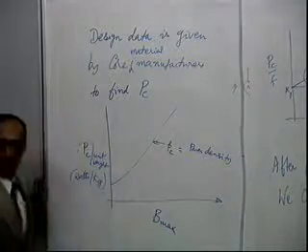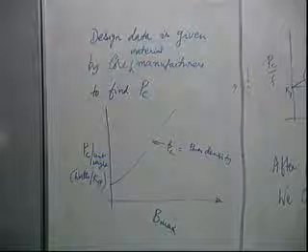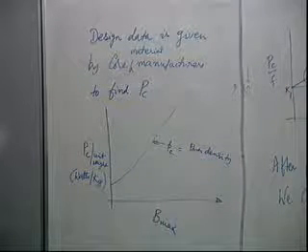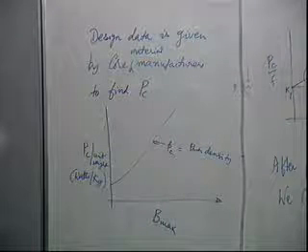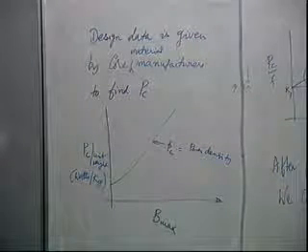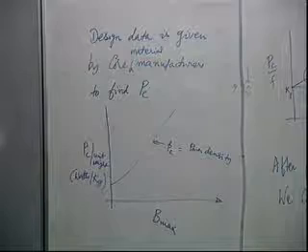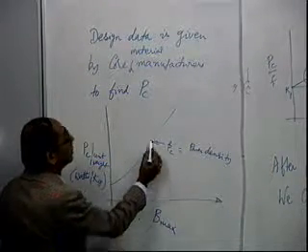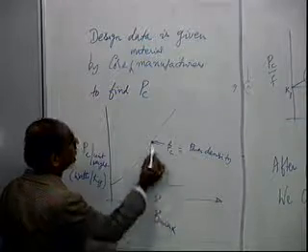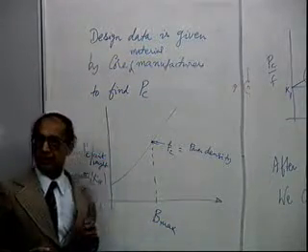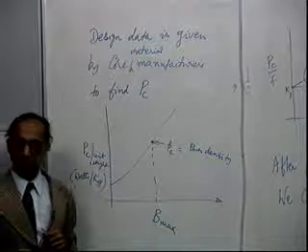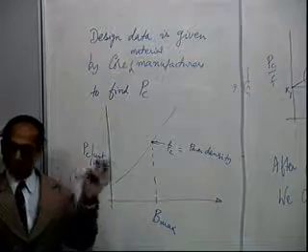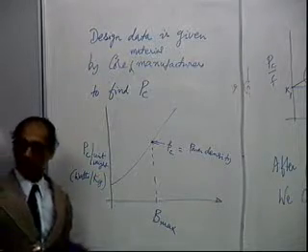That is how much power loss density. But I have given you, in one of the handouts, one of the material properties. So what will you do to calculate the core loss? You know the operating flux density. So for the given flux density, you find out the core loss per unit volume, weight. Then you must know the weight of the core, and this is the total core loss.